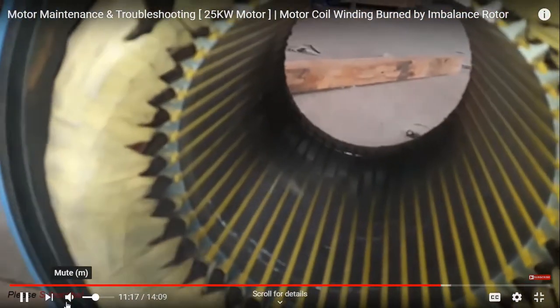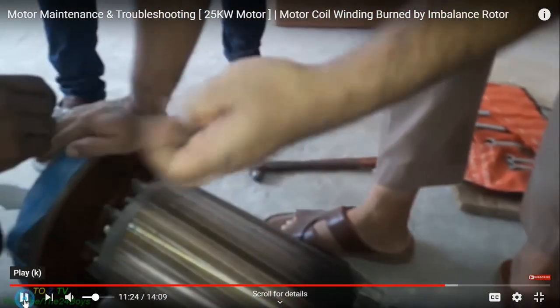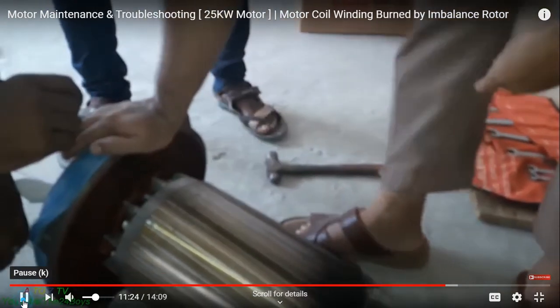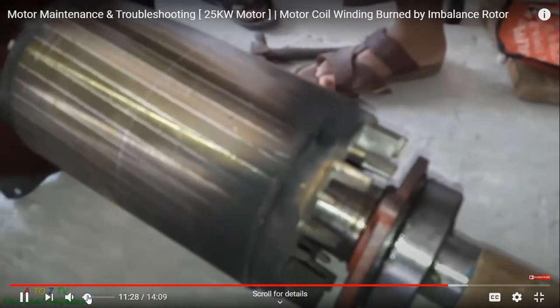The backside, one side is different, that means there's a problem. Look at the backside color, it seems okay because it's a new motor and should look like that, but no, there's a problem with the motor. So you see, these are the different parts of the motor which can be inspected for repairing. There's a metal part with this rotor, and it's not supposed to stay here.